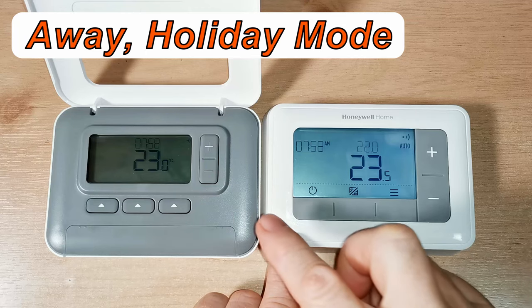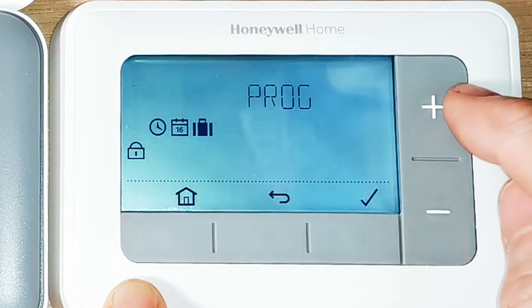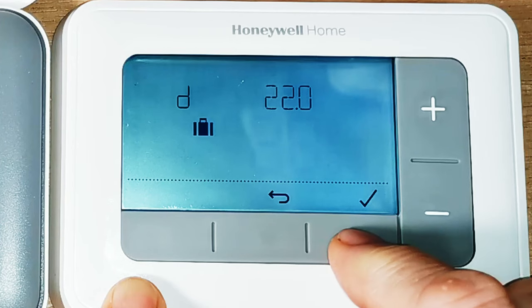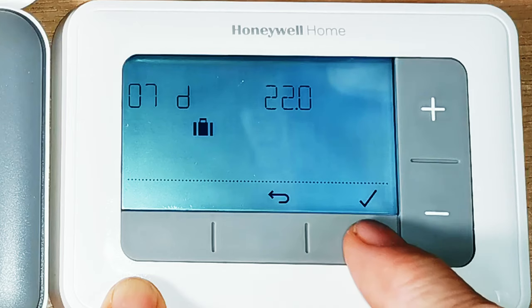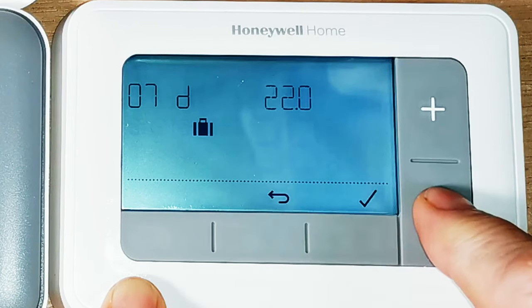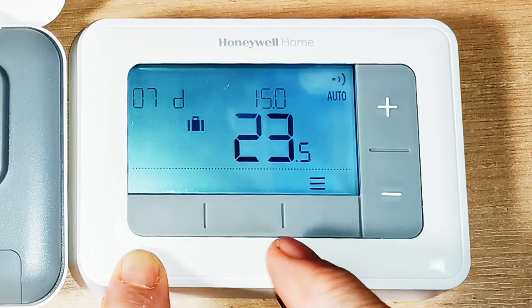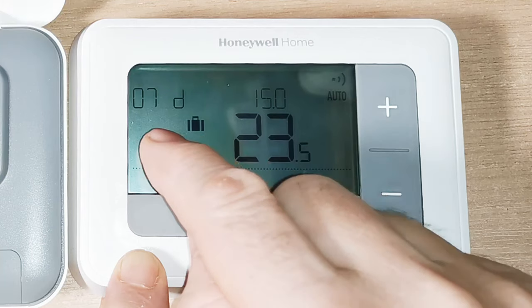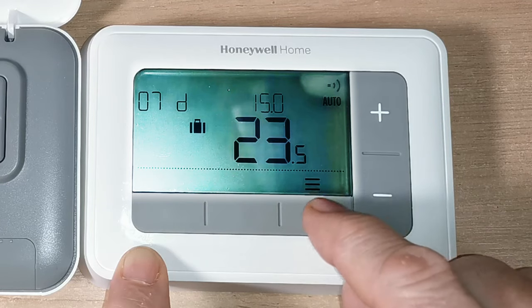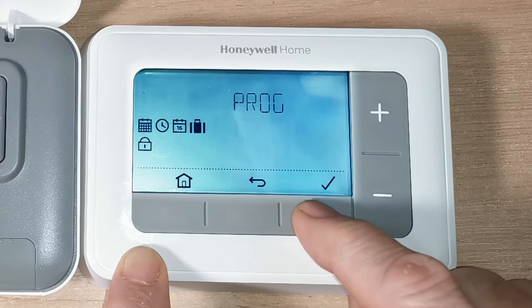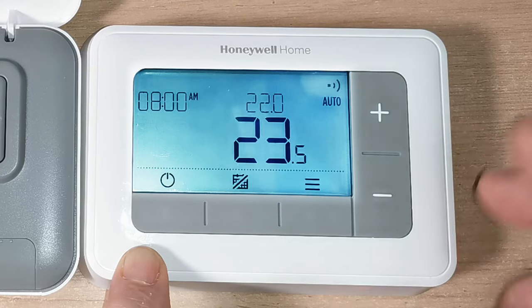Another function that the T4 has that the T3 doesn't is the away button or holiday mode. Push this button and the menu comes up — you can see the suitcase icon. Scroll along to the suitcase and press tick to enter holiday mode. You can now put in the number of days you're going on holiday — say a skiing holiday. Press tick, then set the temperature you want to keep the house at while you're away, for example 15 degrees. Press tick again and it saves. The display will then show a suitcase, the number of days, and the set temperature. To cancel, go back into the menu, scroll to the suitcase, press tick, and that cancels the function.